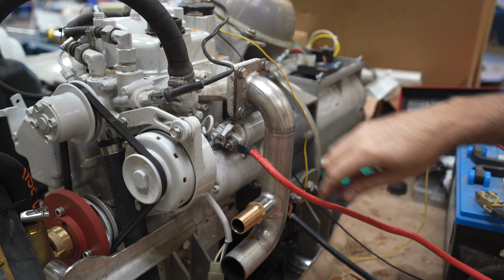Yesterday I did a quick little load test. That's why there are 3 space heaters here. I don't have any video of that, but I can reproduce it. Each of these little space heaters here are 2000 watts. All 3 are connected to the alternator. If I turn on 1, we've got a 2 kilowatt load. If I turn on 2, we've got a 4 kilowatt load. And if I turn on 3, we've got a 6 kilowatt load. But spoiler alert, the itty bitty Perkins is not going to be able to handle 6 kilowatts.